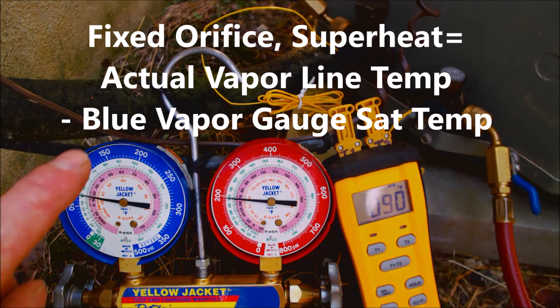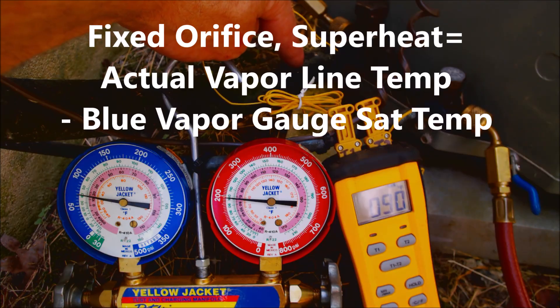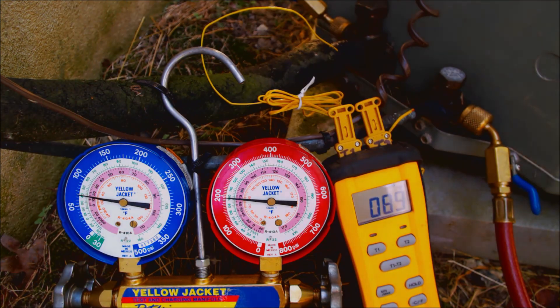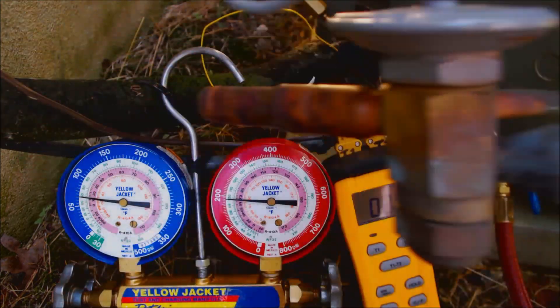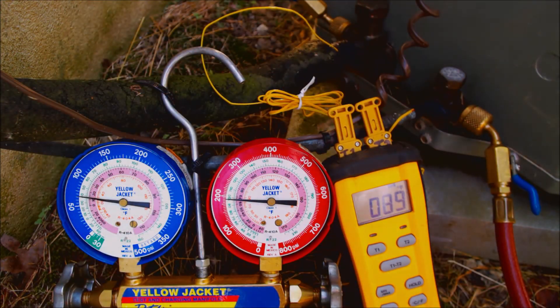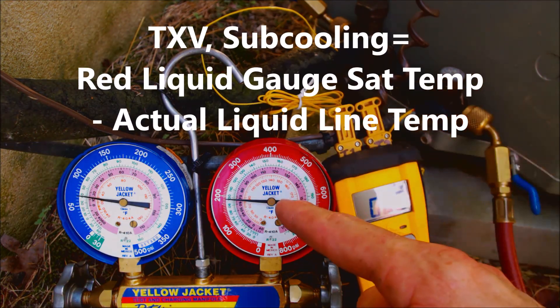If you have a fixed orifice, you're going to be checking superheat, which means you take the suction temperature minus the saturated temperature. If you have something that looks like a thermostatic expansion valve, then you want to be checking the charge with subcooling, which is the saturated temperature minus the liquid line temperature.